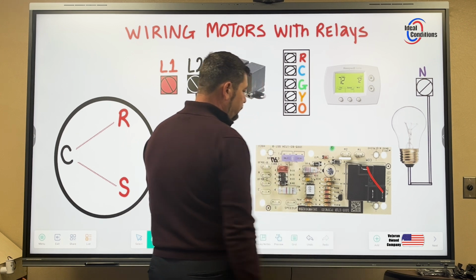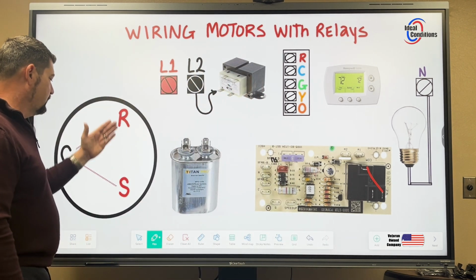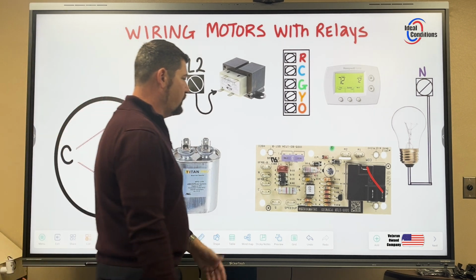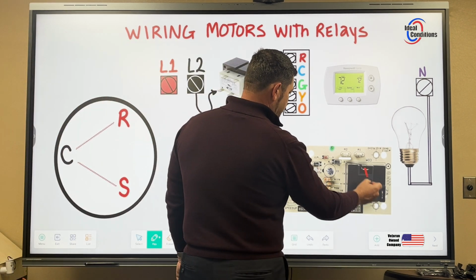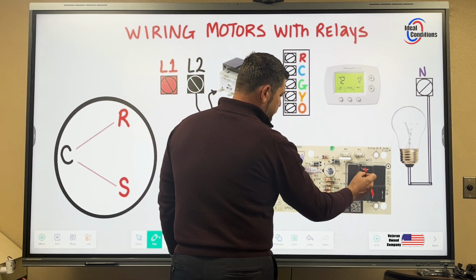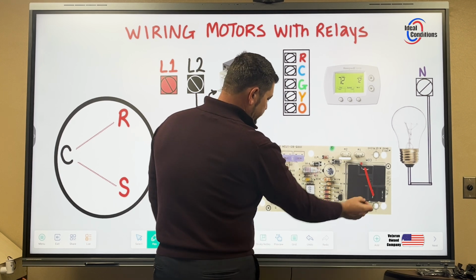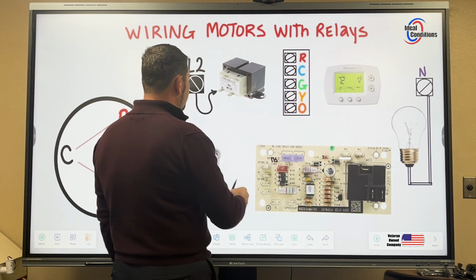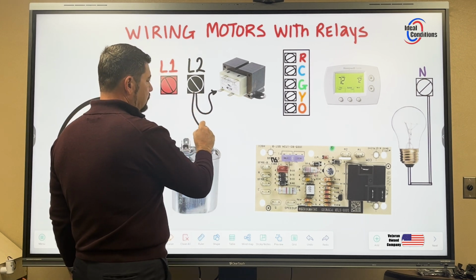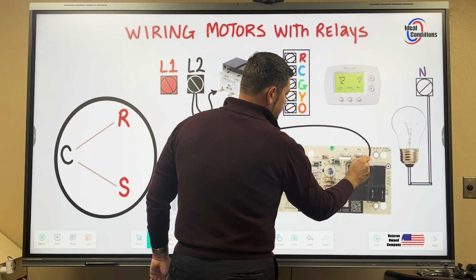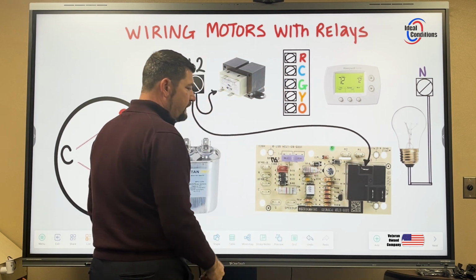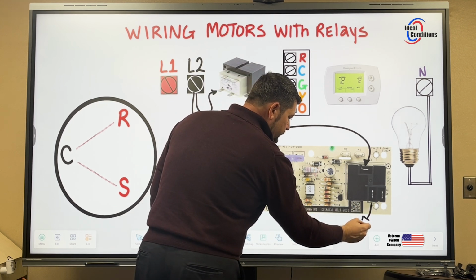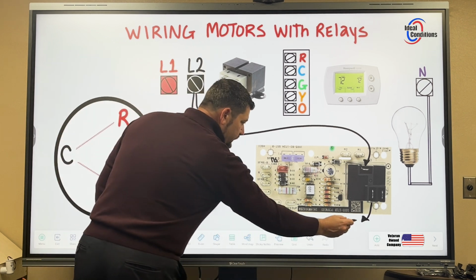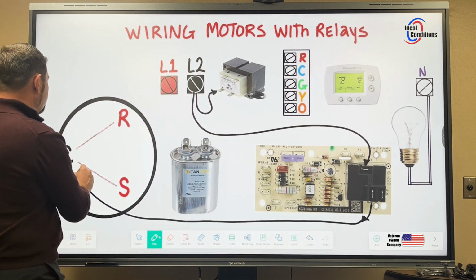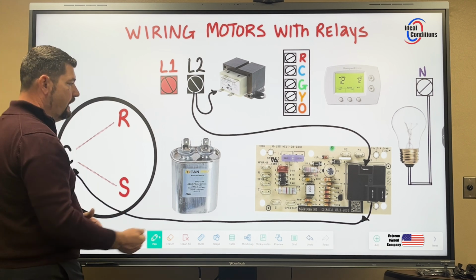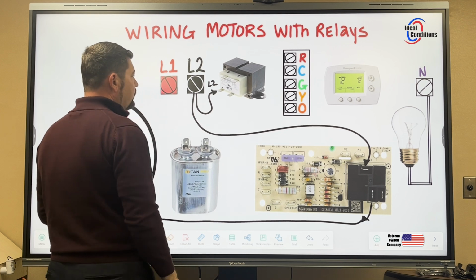So if we wired our motor to this, the moment we give it power on run and start, the motor is never going to turn off. So we obviously aren't going to wire to our normally closed. What we're going to do is wire here to common, so when we get power, common will make normally open. So we're going to come over with L2 and we're going to wire common. Common will be an input, and then out of the normally open terminal, that'll be our output. Okay, we're going to wire this over to common. And now we can go ahead and just start labeling everything, checking things off.